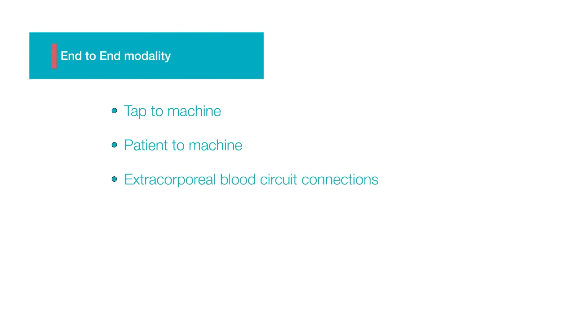While initiating a therapy, you would need to perform four assemblies: tap to machine, patient to machine, extracorporeal blood circuit connections, and machine to patient.